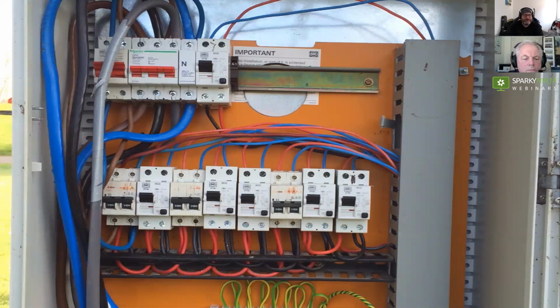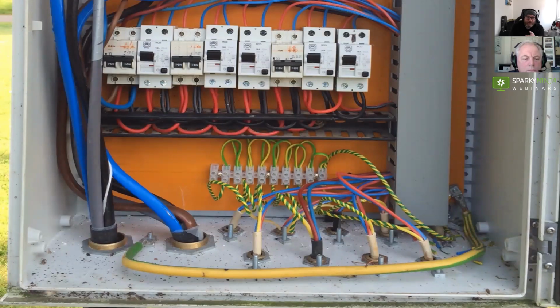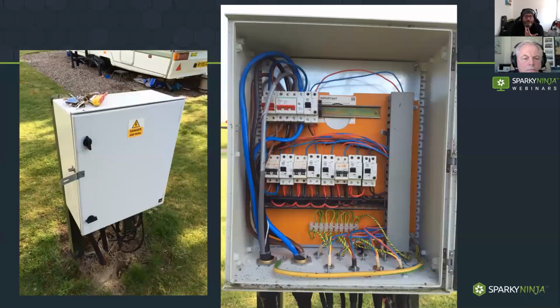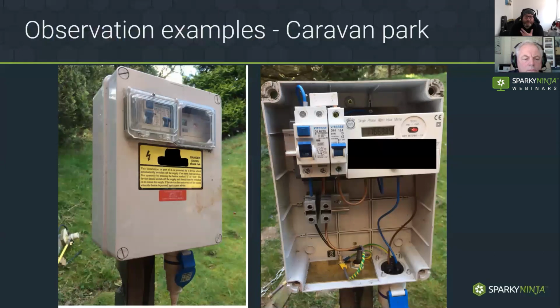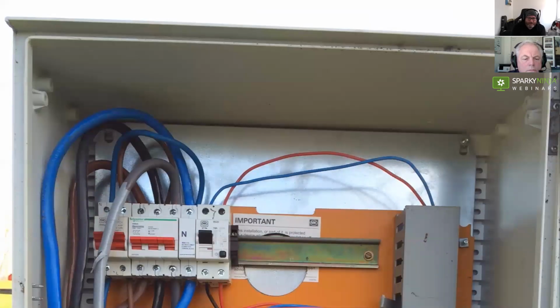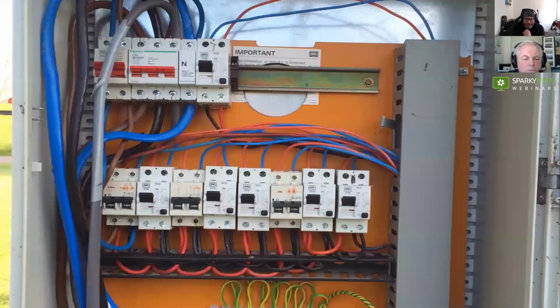And then out the bottom of each of these, or at the top of each of these devices, is one of these at the bottom here. 1, 2, 3, 4, 5, 6, 7, 8, 9 cables. And those are the ones that go to these hookup points here. So it feeds 9 hookup points. But when we look at what we've got in here then, we've got one caravan hookup point which has just got overcurrent protection on the cable feeding it. Then the next one has just got RCDs. So it's a bit of an abomination, really.